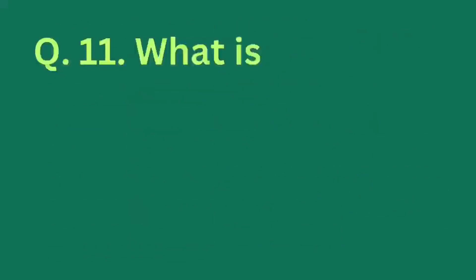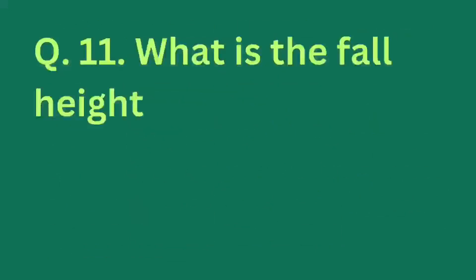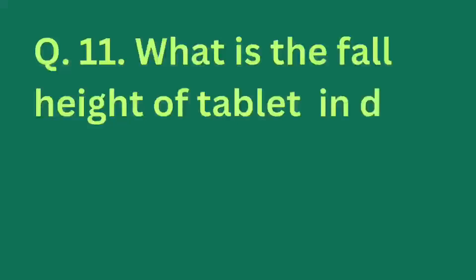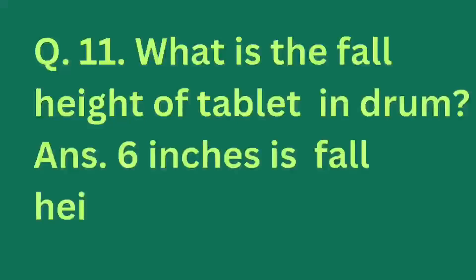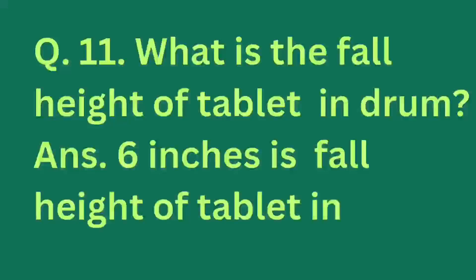Next question: What is the fall height of the tablet in the drum? Answer: The fall height of the tablet in the drum is 6 inches.